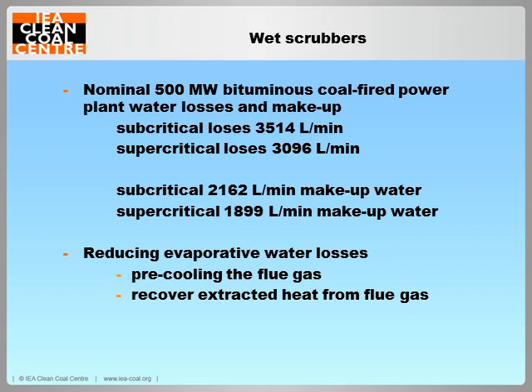Another option is to recover the extracted heat from the flue gas within the steam cycle. This will improve plant efficiency and hence reduce water consumption. Low temperature economizers are widely used in China to recover waste heat in the flue gas to heat the condensate from the turbine.